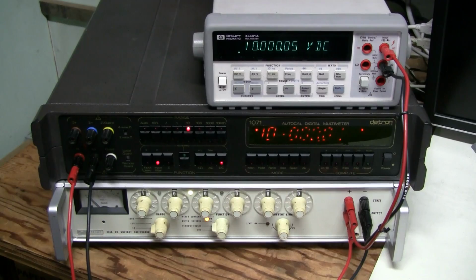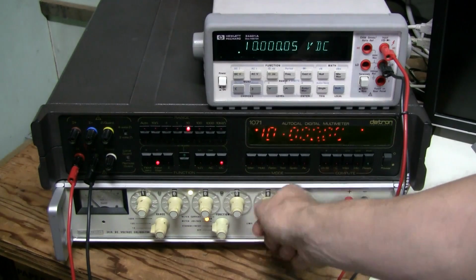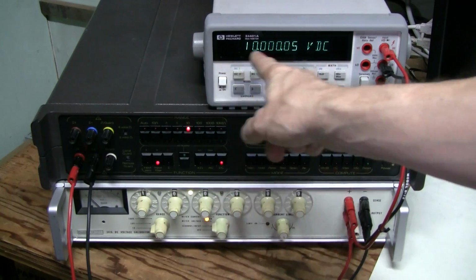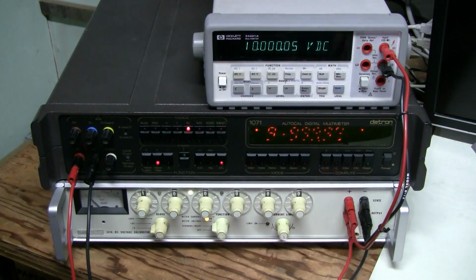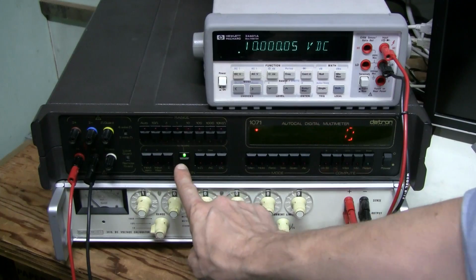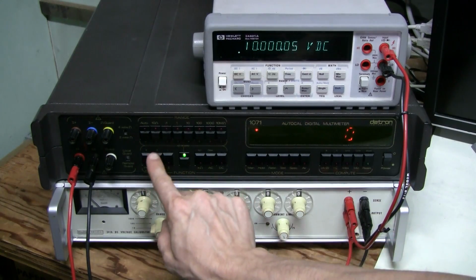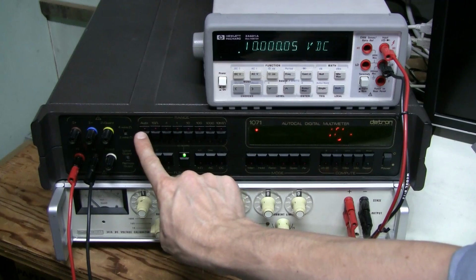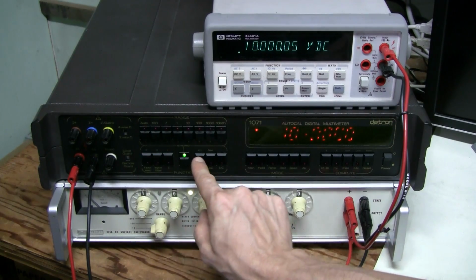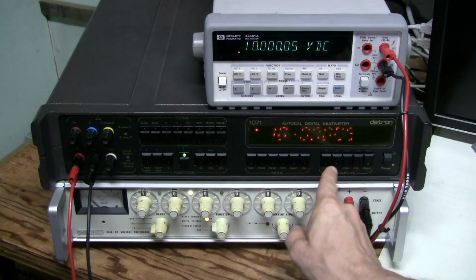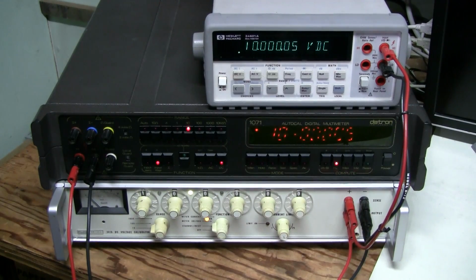And now there are two ways. One is to adjust fluke until we read exactly 10 here and then press gain. Or there is another way. If the reference is not exact, we can just enter manually, like so. 10.00005 and then press gain. So when this light disappears, we should be done. That's it. Full scale is set.